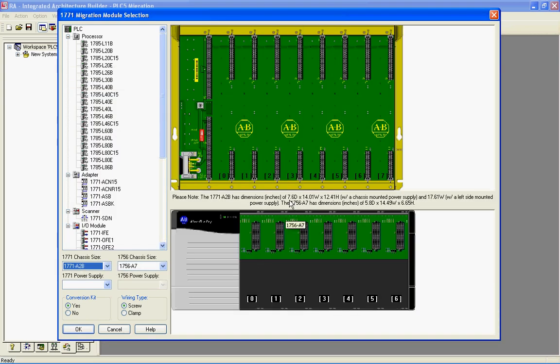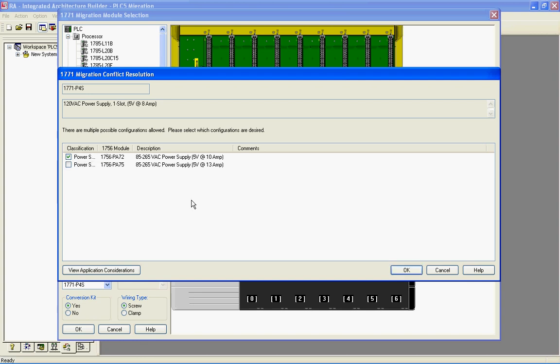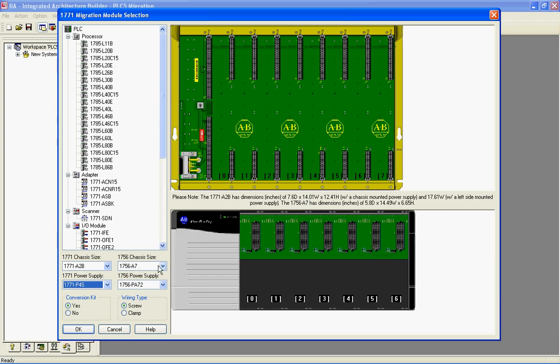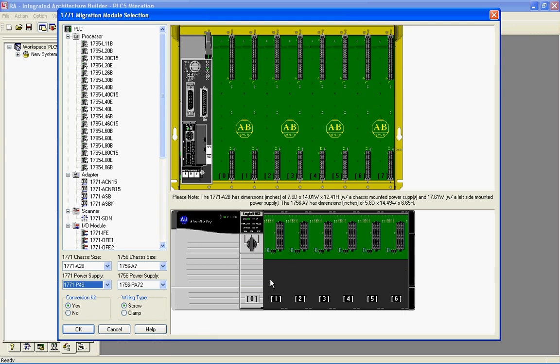You'll notice it drops the icons on the images on the screen as I do that. I'm going to pick a P4S Power Supply, and I'll say I want a 1756-PA72 Power Supply to replace that. I can start dragging and dropping items into the PLC-5 chassis and let it do the conversion for me. So let's pick an L40E PLC-5 processor, and I'll say I want to go with a ControlLogix 1756-L62 processor in its place.